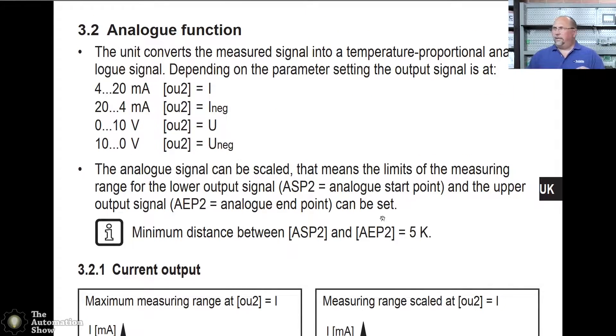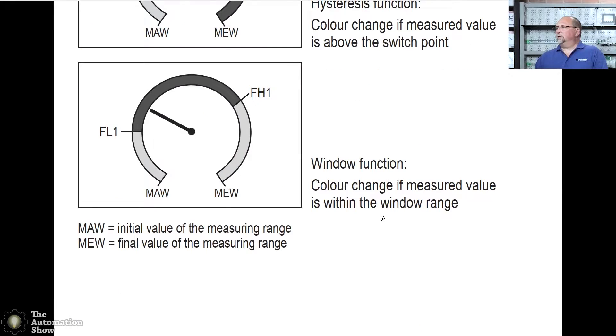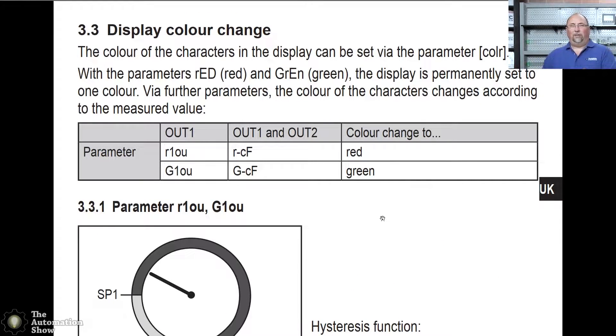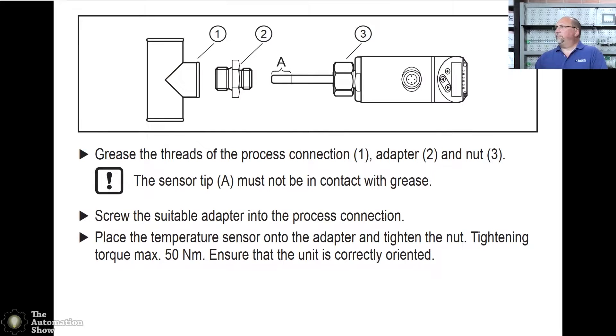Now it has four different analog output options. We're going to start with zero to 10 volts because in testing this with some of the micros, they only had zero to 10 in. If we have time, we'll also try 4 to 20 milliamp. One nice feature I like about this sensor is you can change the color of the display. When the temperature's in the 65 to 80 degrees range, we're going to have a green display. But when it either gets too cold or too hot, we're going to change the display to red, which is really cool. I love that feature. If you're in the facility, you can look down if you've got a bunch of these sensors, and if any of them show up red, you know there's a problem there.